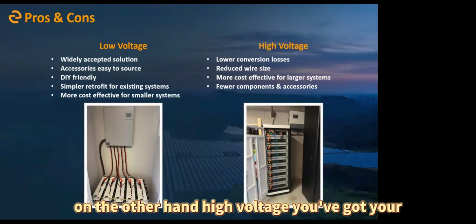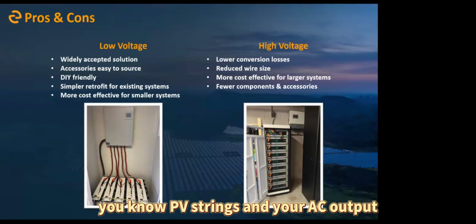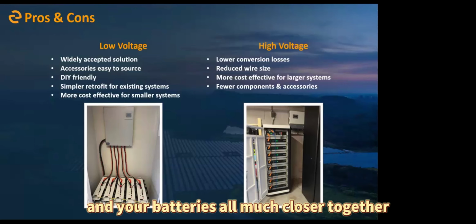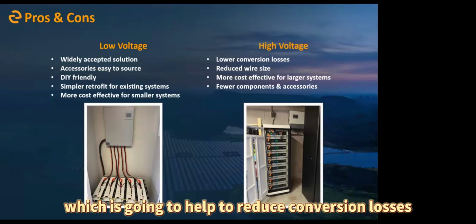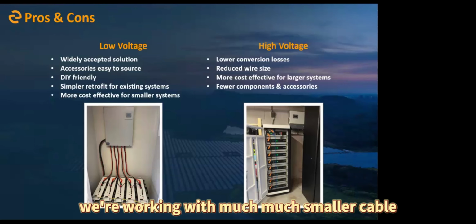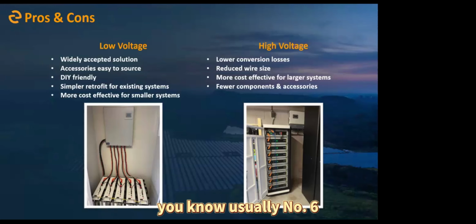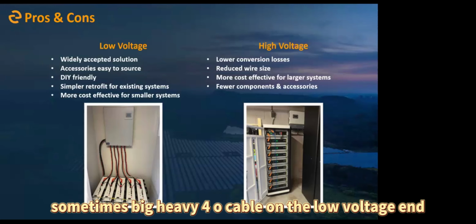On the other hand, with high voltage you've got your PV strings, your AC output, and your batteries all much closer together, which helps reduce conversion losses. We're working with much smaller cable, usually number 6 or number 4 gauge max, as opposed to sometimes big, heavy 4-aught cable on the low voltage end.